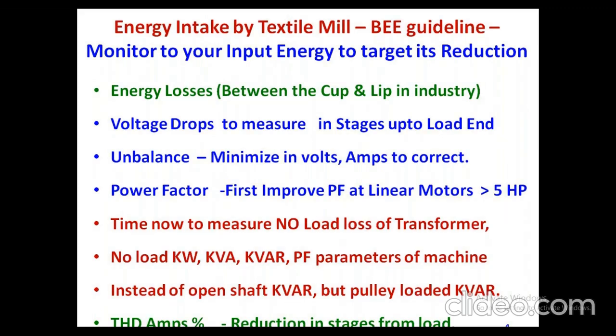what is the voltage drop when, out of 10 machines running, one machine is switched on and off. If you are able to see the voltage drop in the next machine, it shows there is definitely a dry contact coming to the machine from the SSB to the machine. These are all the things. See, an energy auditor does not rely on the readings we take in the industry. We just see what transients are happening when we are taking the readings.